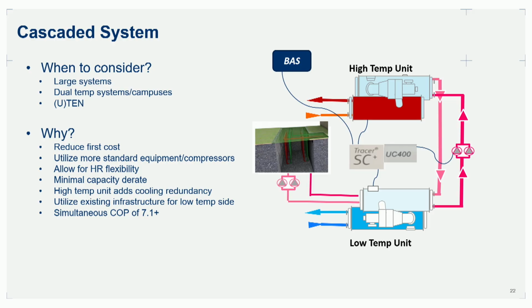Utilizing existing infrastructure is another thing. So if you've got a building that just put a brand new water-cooled chiller system in 5-10 years ago, and now you're coming in trying to get them to go to a high-temperature heating application, instead of ripping out those chillers or abandoning them in place and putting a whole new system on, we can use that existing equipment as the low stage, and all we need to do is add that high stage. So we're really only adding half of the system to what they've already got existing.